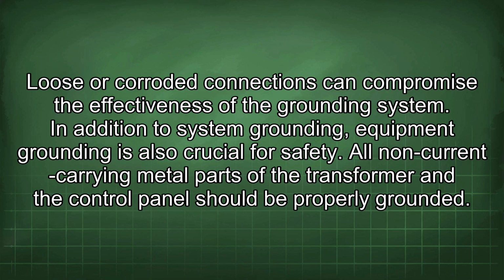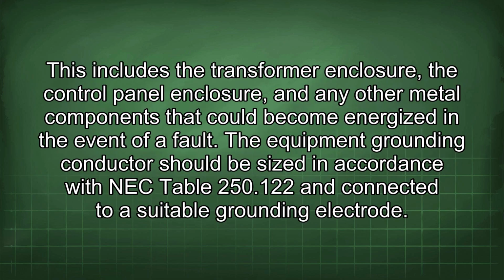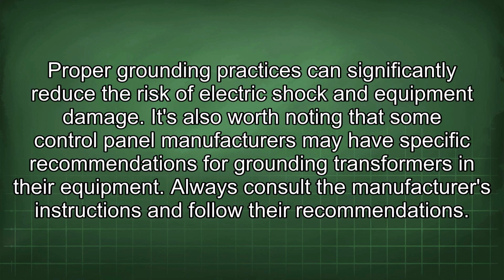In addition to system grounding, equipment grounding is also crucial for safety. All non-current carrying metal parts of the transformer and the control panel should be properly grounded. This includes the transformer enclosure, the control panel enclosure, and any other metal components that could become energized in the event of a fault. The equipment grounding conductor should be sized in accordance with NEC Table 250.122 and connected to a suitable grounding electrode. Proper grounding practices can significantly reduce the risk of electric shock and equipment damage. It's also worth noting that some control panel manufacturers may have specific recommendations for grounding transformers in their equipment. Always consult the manufacturer's instructions and follow their recommendations.